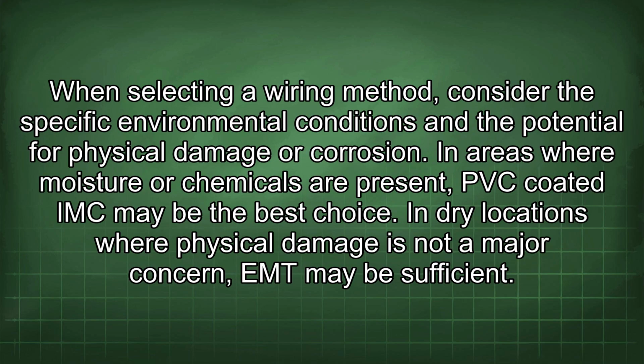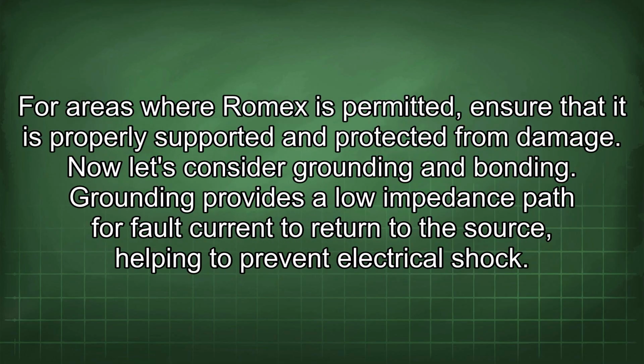When selecting a wiring method, consider the specific environmental conditions and the potential for physical damage or corrosion. In areas where moisture or chemicals are present, PVC-coated IMC may be the best choice. In dry locations where physical damage is not a major concern, EMT may be sufficient. For areas where Romex is permitted, ensure that it is properly supported and protected from damage.